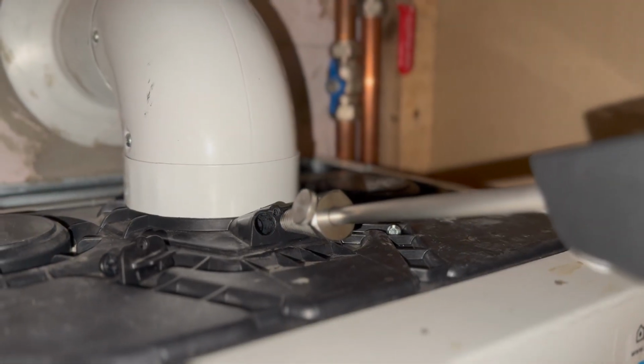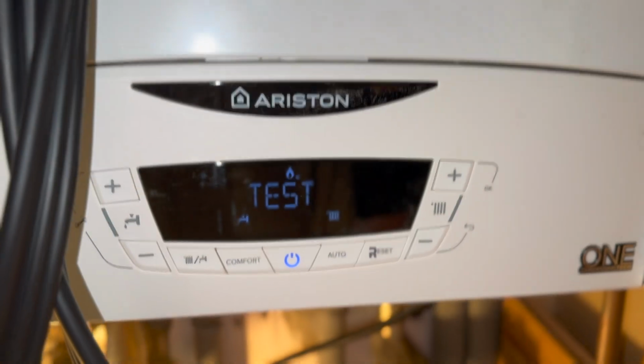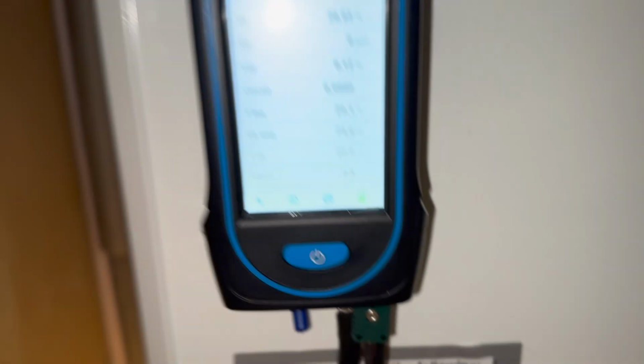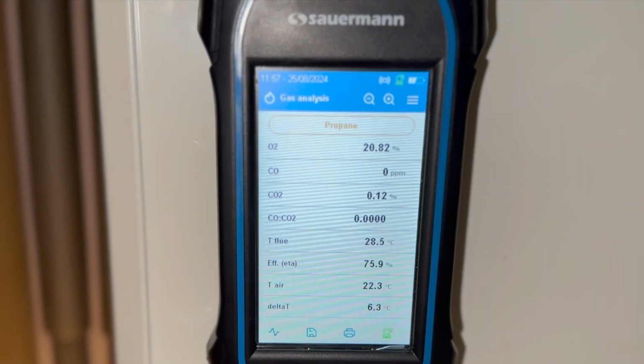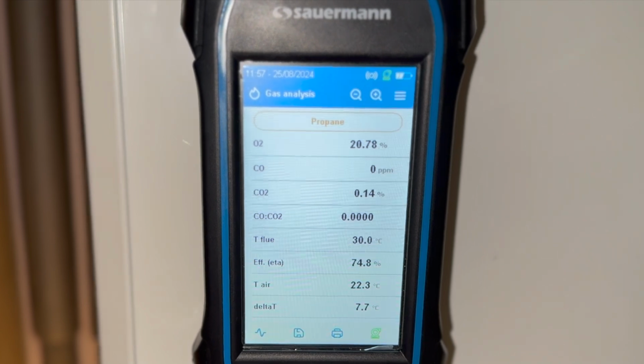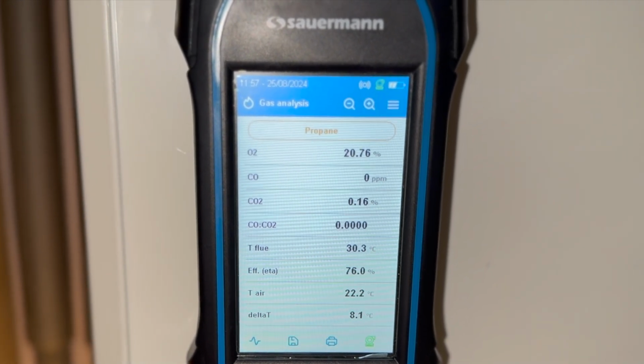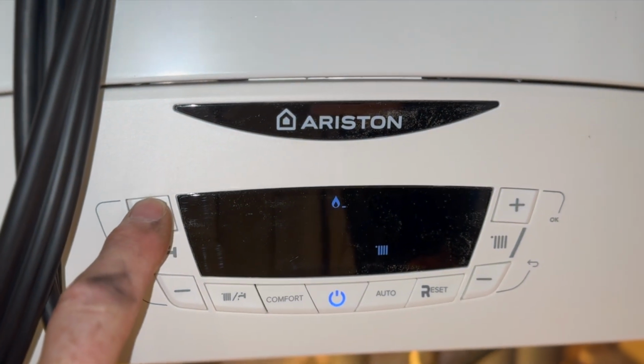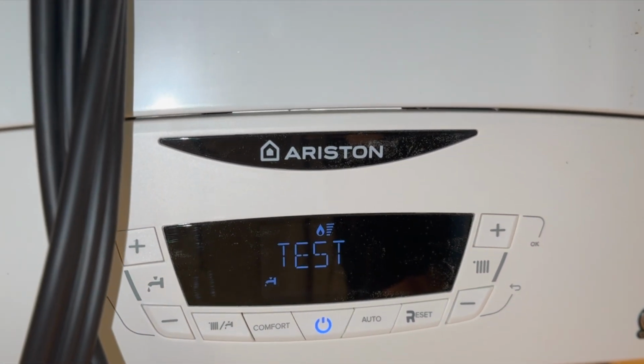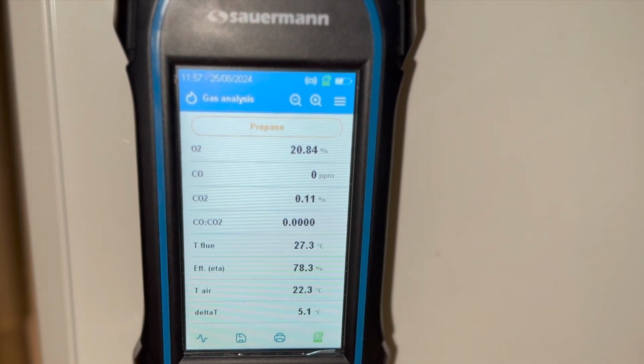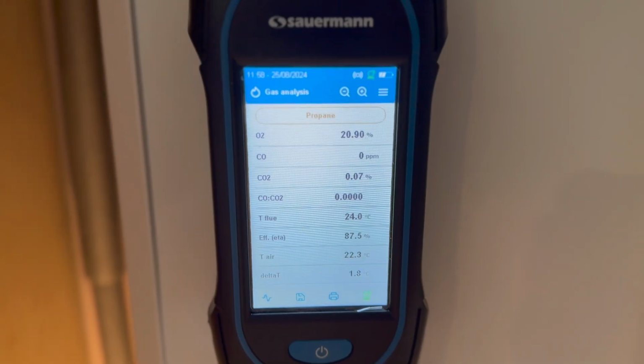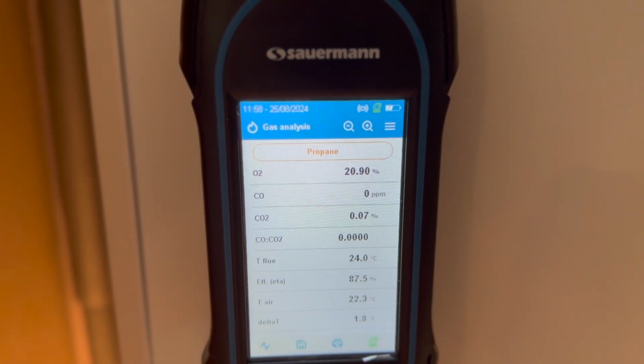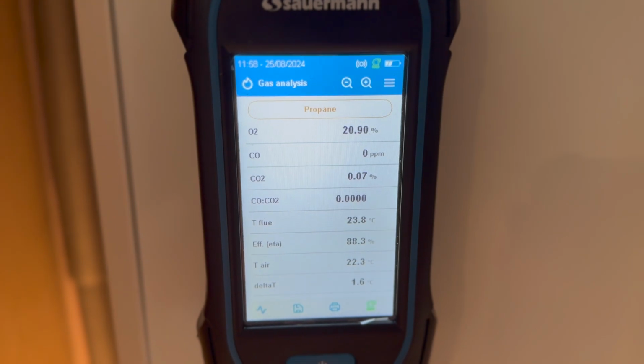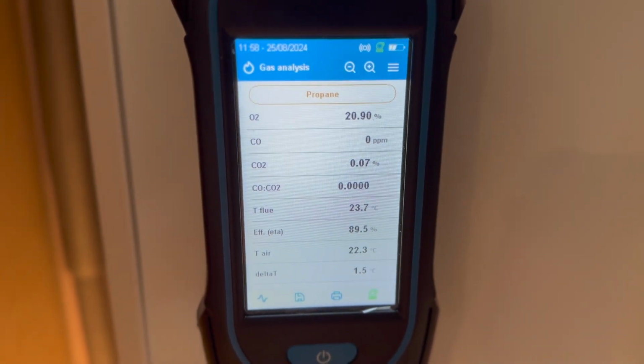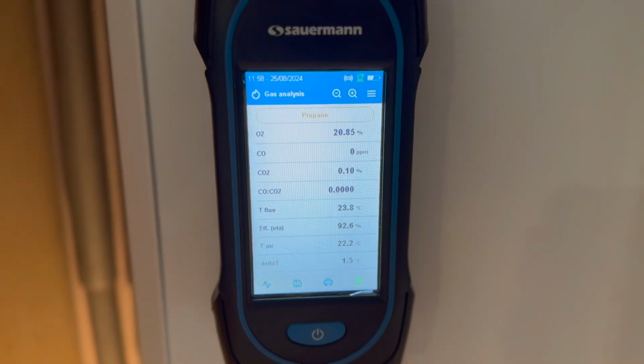I will change the probe over to the flue integrity test point. We are still in minimum and we are reading an O2 of 20.6, no CO, a CO2 of 0.15 with zero ratio. So that's looking good. Let's put it back into high fire. Give it a few minutes and then let's see what our readings are then. So in high fire we have an O2 of 20.9, we have zero CO, and we have 0.07 on our CO2 with no ratio. So that's tickety boo also.